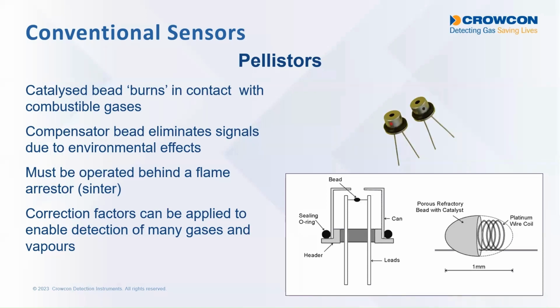Traditionally, our only viable sensor option was the one that you can see on the screen, which is called a pellistor, or otherwise known as a catalytic bead. These were developed in the 1950s by the Coal Mining Research Institute for detecting methane in mines, a bit of a more reliable method than using a Davy lamp or a canary. And they operate by heating up a coil of wire in a circuit, and that hot coil of wire is coated in a bead that's catalyzed to react with gas.